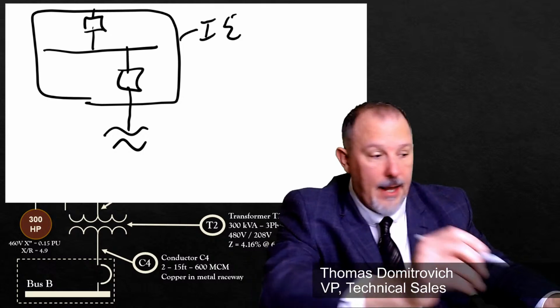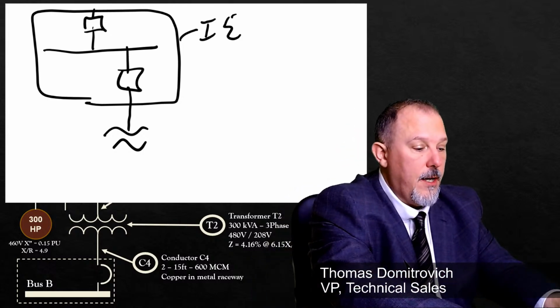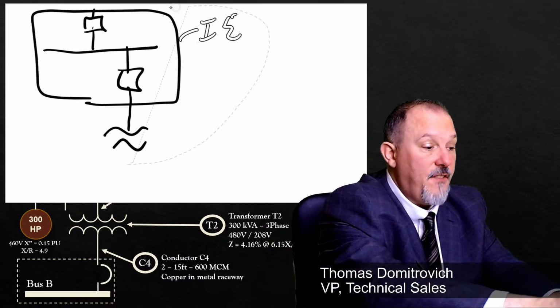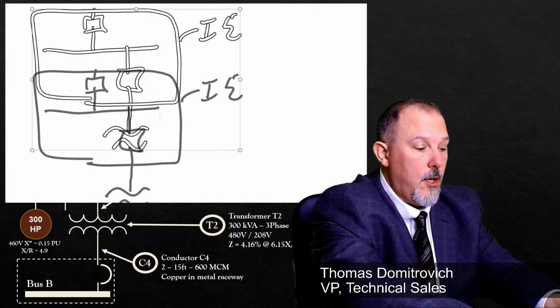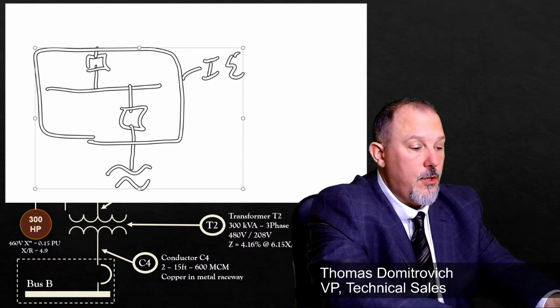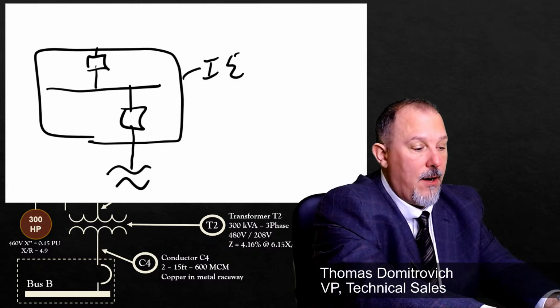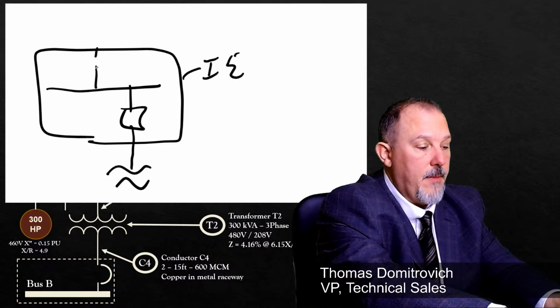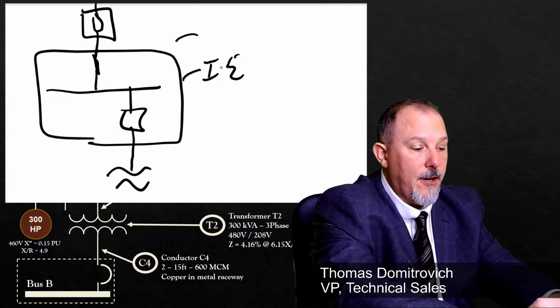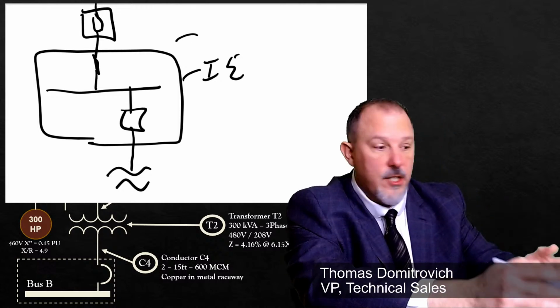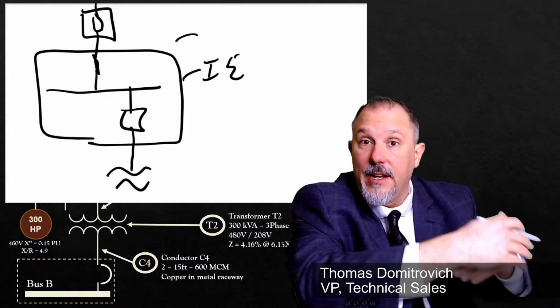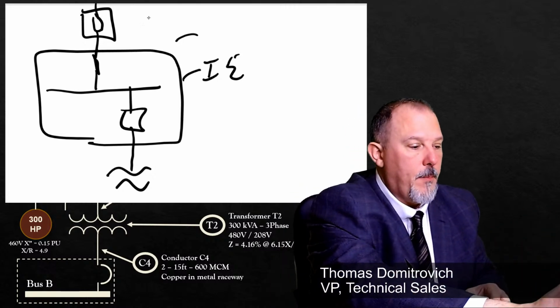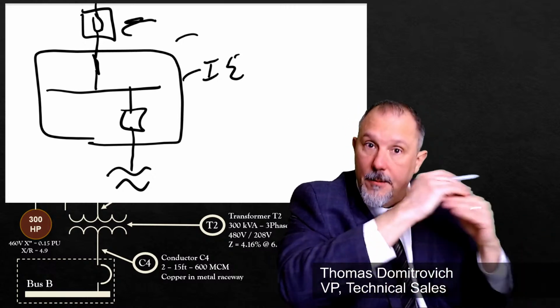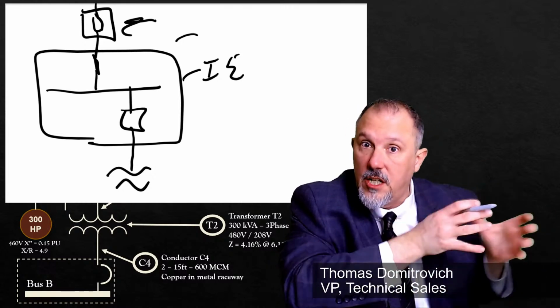So what did we say about reducing the incident energy? A safety by design principle would be to pop that main breaker out, take the main breaker out of this panel board, put it in its own enclosure, right? So now the incident energy in this switchboard is not dependent upon the main, because I got rid of it. Now it's dependent upon the upstream overcurrent device, which is that device, which is in its own enclosure.